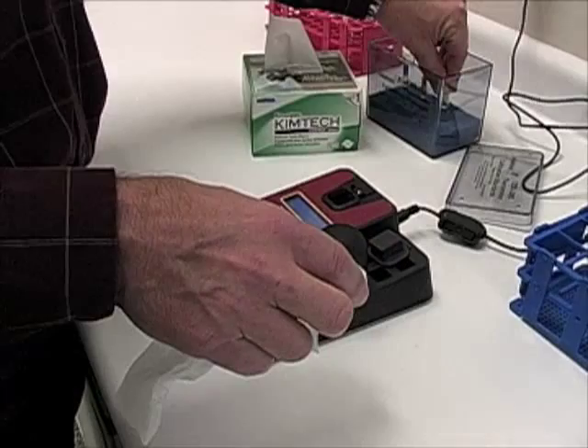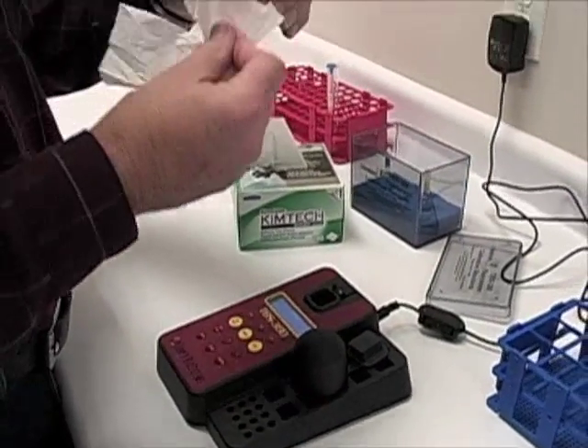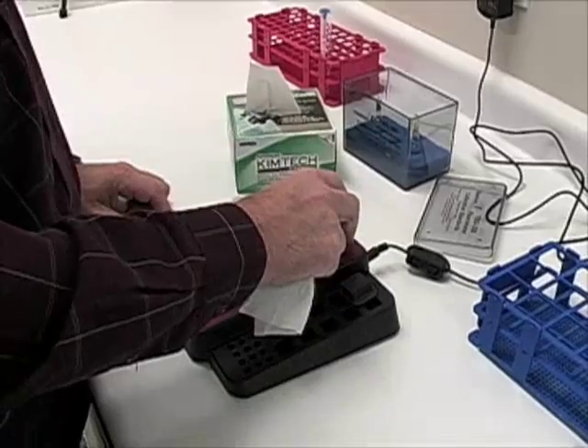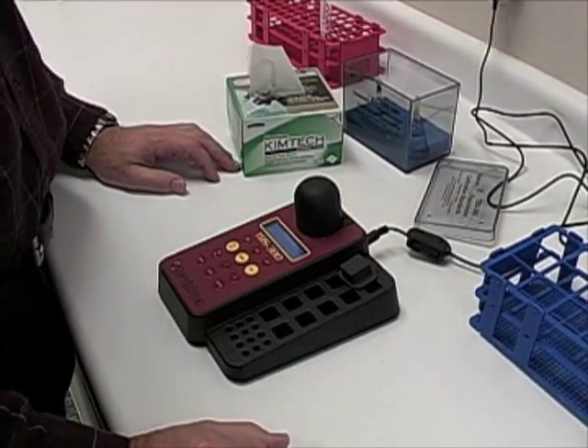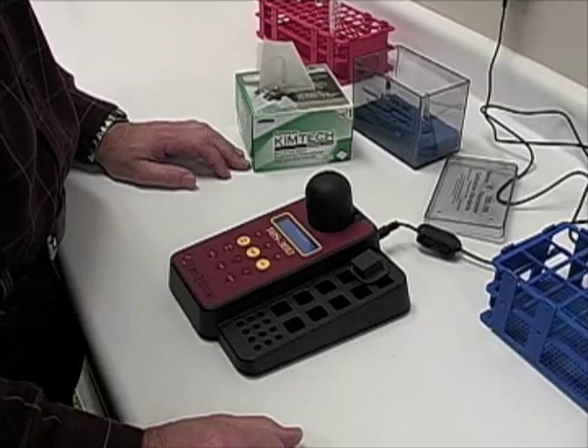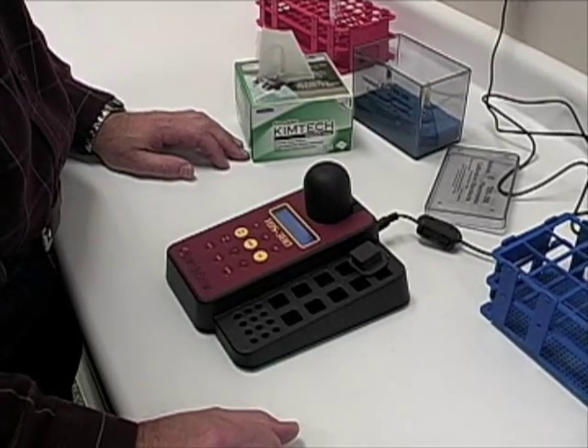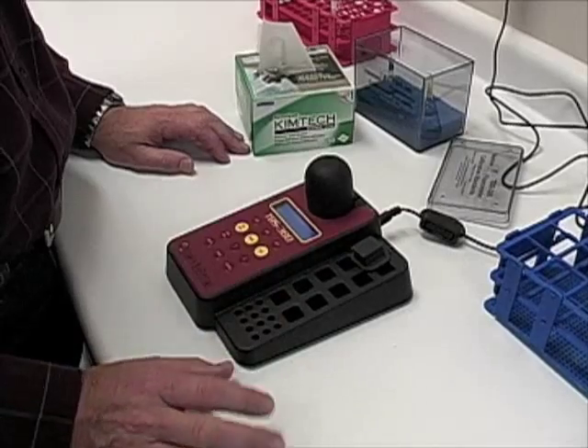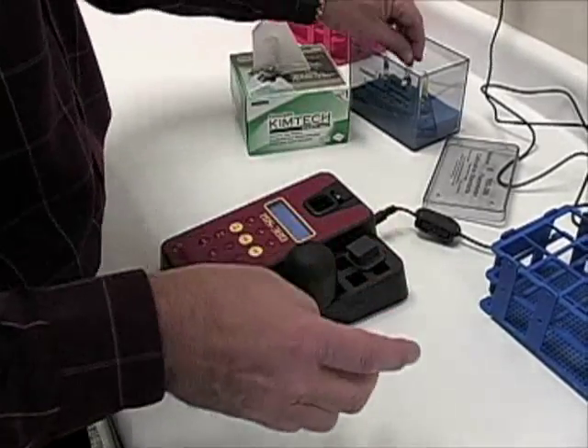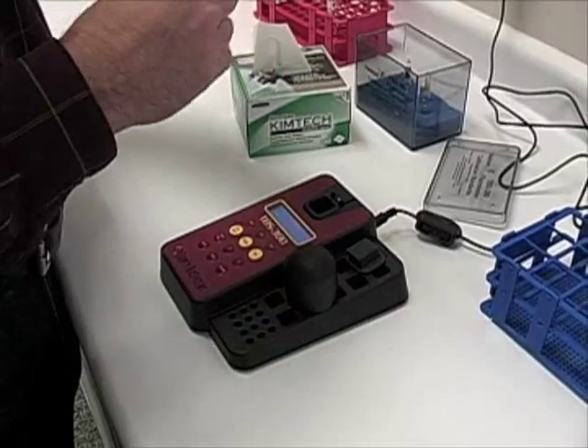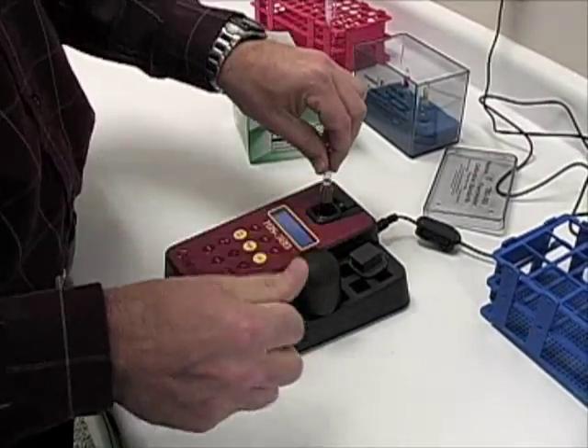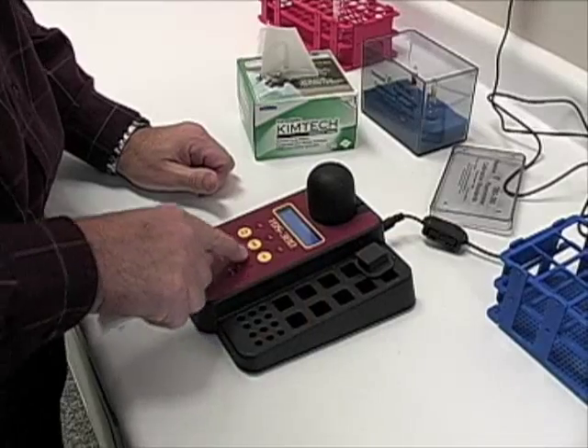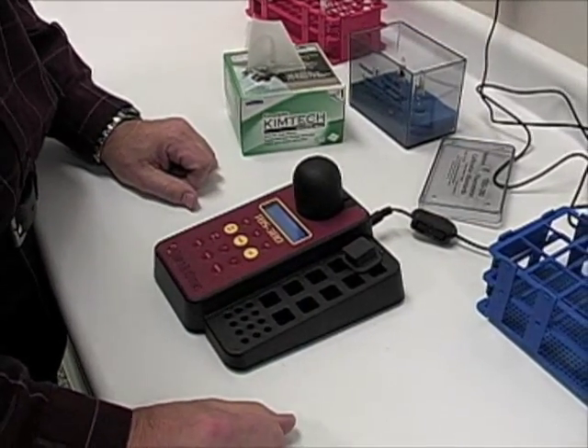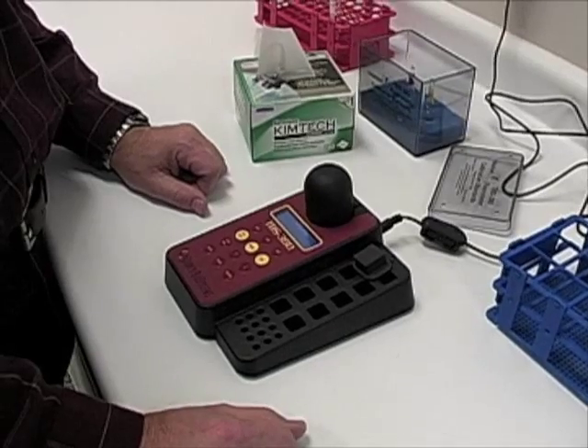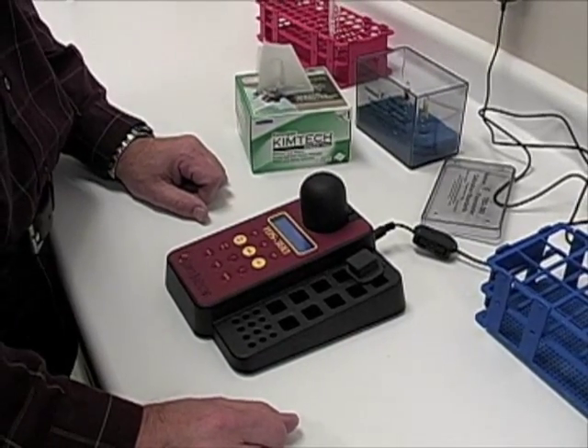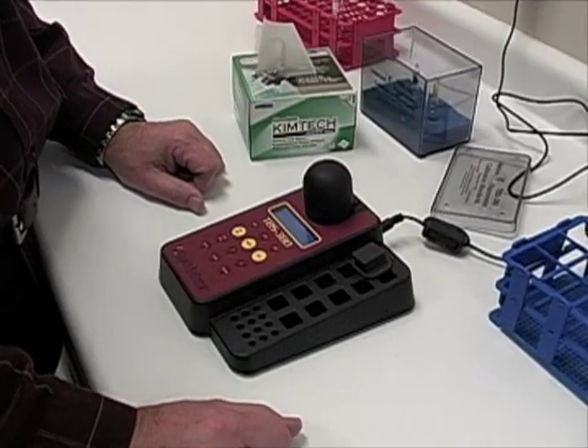You can also just check by putting the high calibrator back in the machine, hitting read, and it should be close to 160, which is how it was calibrated. This is actually 159.5. You can also check to make sure the low calibrator should read approximately 0. Hitting read. These are just double checks to make sure that everything is calibrated correctly. And it reads 0.339. So the machine is properly calibrated now.